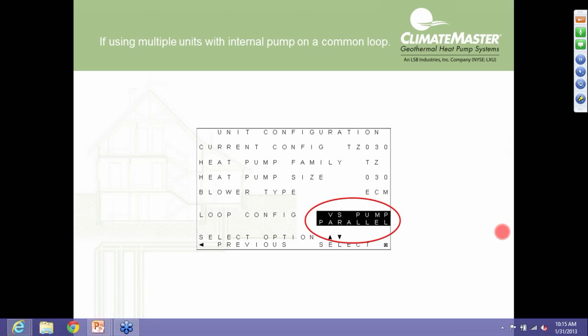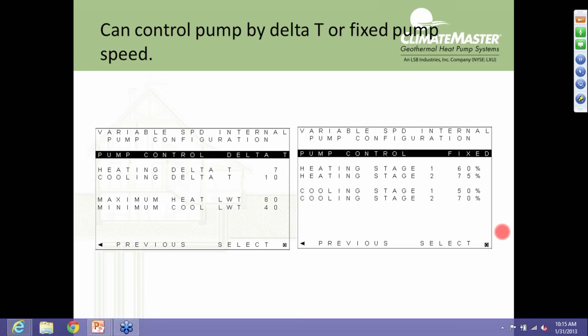Now, the pump or the valve is controlled via delta T. So we're measuring entering water and leaving water, and we're going to control the speed of the pump based on delta T, the temperature difference from entering water to leaving water. Now, I'll talk a little more about where you can adjust that here in a moment.